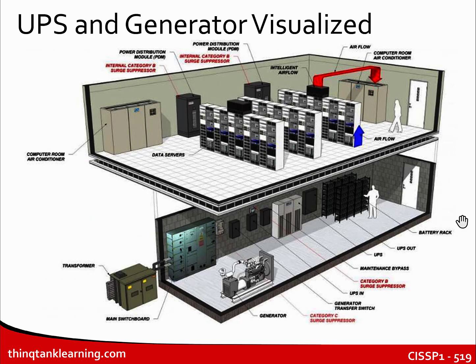So here's a pretty diagram of what a commercial data center might look like. You've got your racks, you've got your intelligent airflow system with hot and cold aisles. You've got your air conditioning unit, and then you have your power distribution modules, which have your intelligent switching systems to go from battery power to generator power. You've got a generator, your generator transfer switch, which usually will operate automatically. The one I have at my house is manual. But your UPS maintenance bypass is where you can switch to alternate power sources if you're trying to implement some sort of maintenance and so on. So these are the kinds of things that you might see.